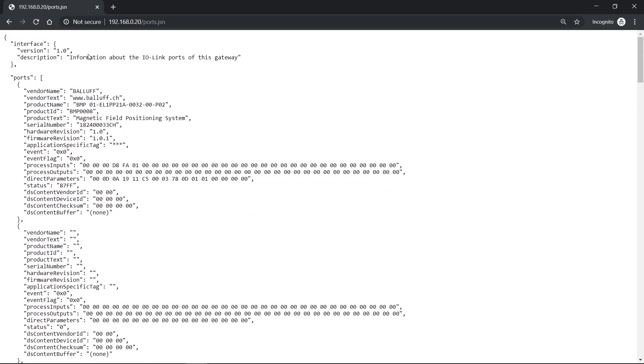Every Ethernet-based IO-Link master from Balluff has this web service. And the good thing about this web service is that the web service is provided by the web server of the master. And as such, it is independent from the controller you have connected, so it's independent of your connected PLC, and also independent of the fieldbus communication.